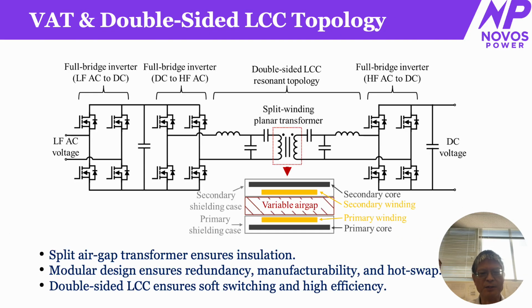The split winding transformer is a design that separates the low voltage and high voltage windings so that we can realize a very high insulation, up to 1,000,000 volt insulation. Typically, you need about 100,000 volt for the insulation. So in this design, we are able to do that. In the meantime, we also have the double-sided LCC topology to form the resonant condition for the switching device so that we can realize softer switching and reduce current on the transformer. By doing this, we can increase the system efficiency by 0.2%.